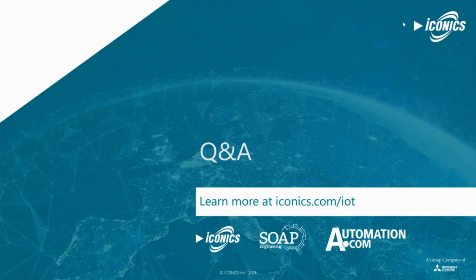Sure. As far as trending goes, on the on-prem solution, the redundant servers on the vessel collect that real-time data. As fast as it's collected, it's also stored in the historian. Everything in the historian is accessible through trending, so it's not set to a defined limit — it could go up to years of data. It just depends on how much data the customer has.